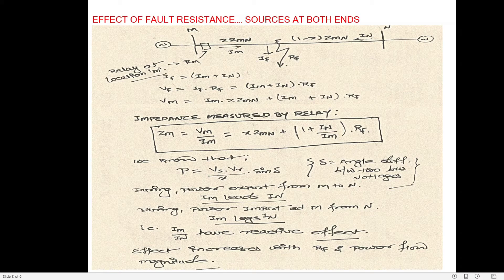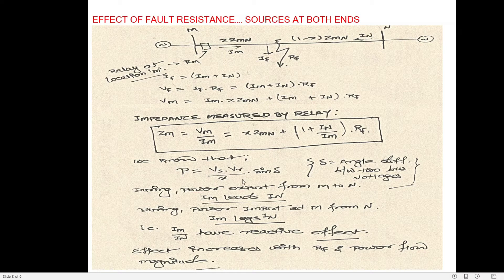In an AC system, power flow between bus M and bus N is possible only when there is an angle difference between the bus voltages. Power is transported from M to N if VM leads VN, and imported from N to M if VM lags VN. This is given by the equation P = Vs·Vr / X × sin(δ), where δ is the angle difference between the two bus voltages.